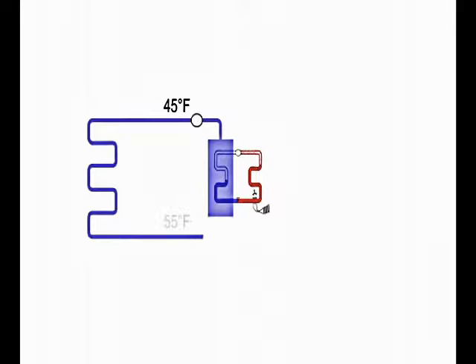Air performs reasonably at carrying cold air, but water is better at heat exchange and does a superior job keeping cold over long distances. For this reason, many buildings and some campuses or city districts utilize chilled water. In this regime, pumps carry water chilled on the evaporator side, which is to say the cold side of the compression refrigeration loop, to sometimes distant air handling units.